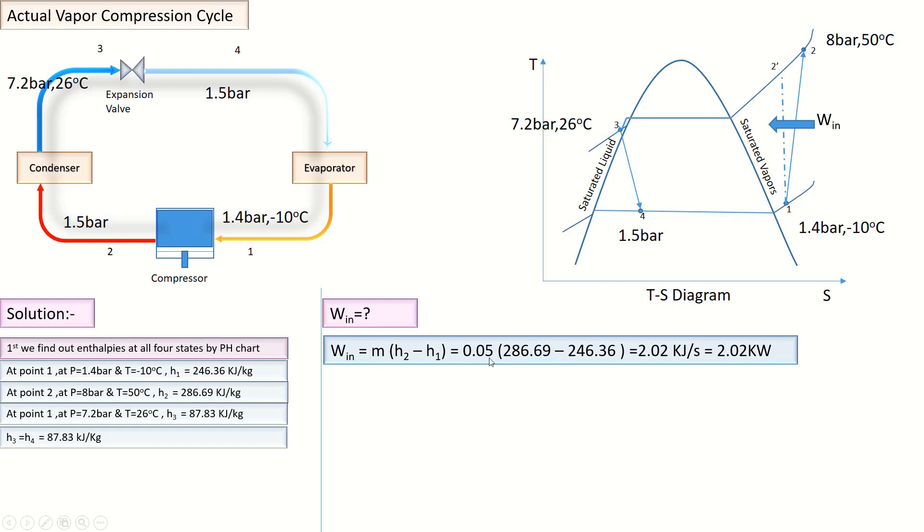Mass flow rate is given as 0.05 kg/s. Enthalpy at Point 2 we have found is 286 kJ/kg and enthalpy at Point 1 is 246 kJ/kg. After putting the values and calculating, we get W_c = 2.02 kilowatts as the required power of the compressor.